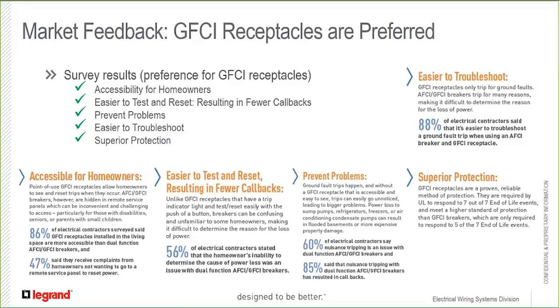Circuit breaker manufacturers are also producing EMI filters to reduce the nuisance tripping with their dual function devices. These are things that need to be taken into account when deciding how to meet the code for kitchens and laundry rooms. And finally, the fifth most popular reason as to why GFCI receptacles are preferred is the superior protection they offer. GFCI receptacles are proven, they're reliable, they've been around for 50 years. They are required to respond to 7 out of 7 end-of-life events by UL, whereas GFCI breakers are only required to respond to 5 out of 7 end-of-life events. And so as appliances in kitchens and laundry rooms become more and more electrically sophisticated, the nuisance tripping issues associated with dual function AFCI, GFCI circuit breakers are becoming more and more problematic.